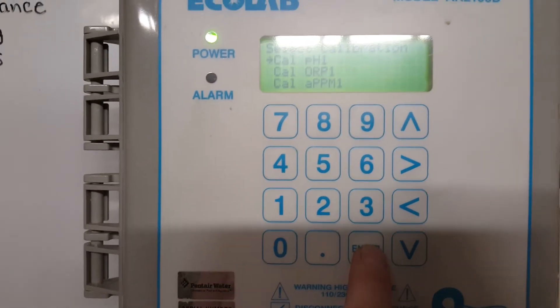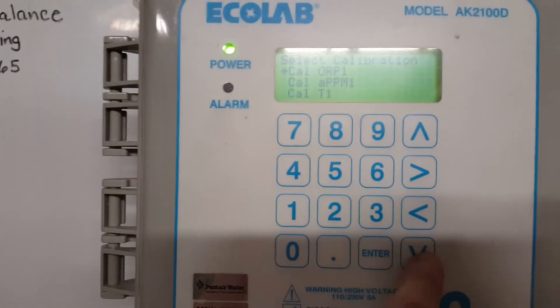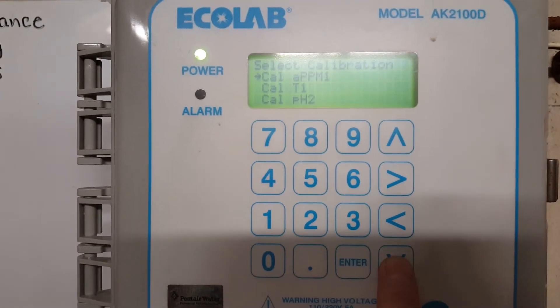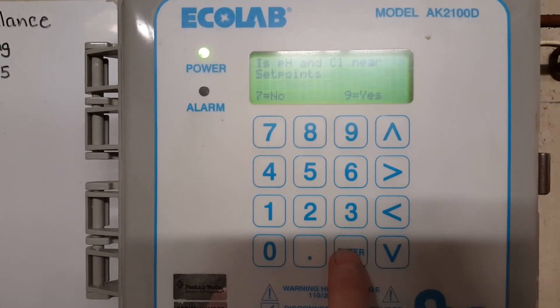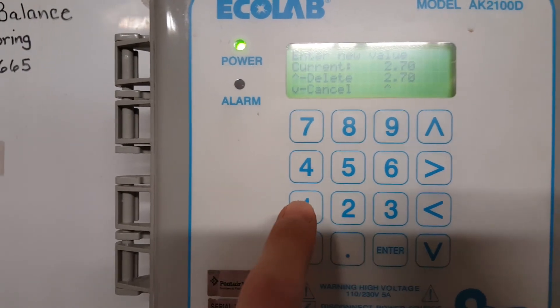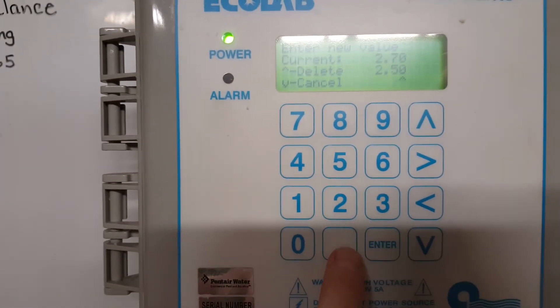That takes you back to the calibration menu. Then go to PPM1, which is your chlorine. Hit Enter, then enter 9 for Yes. You then need to enter your reading — in my case that was 2.50.